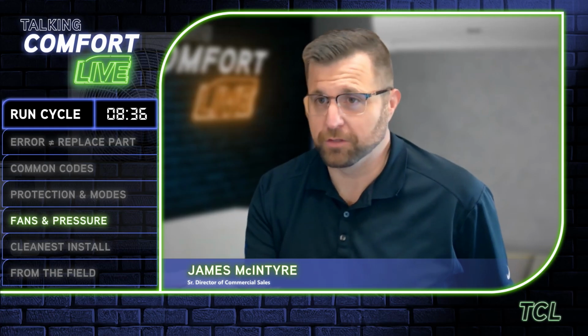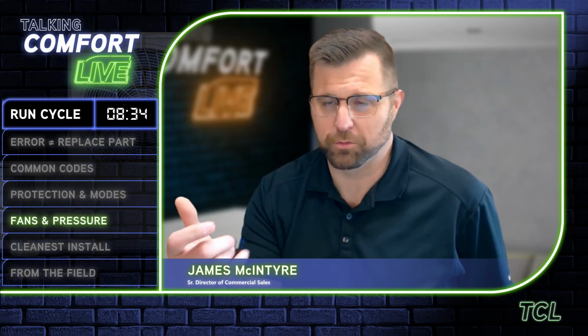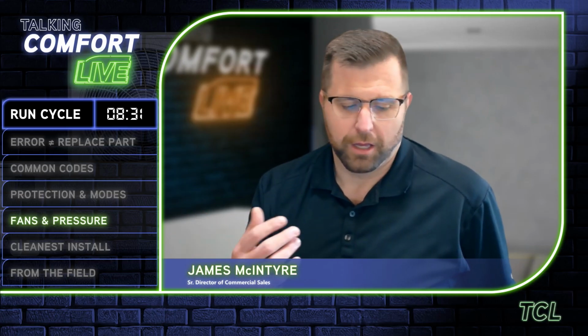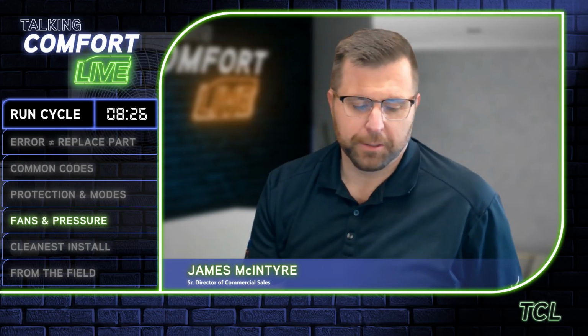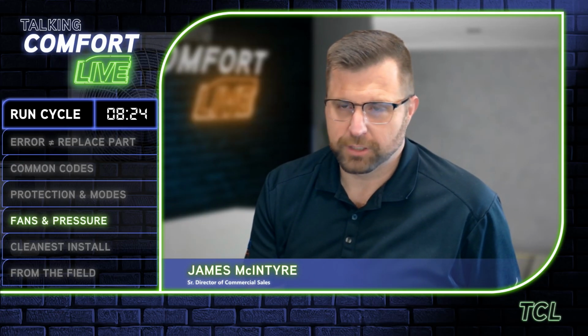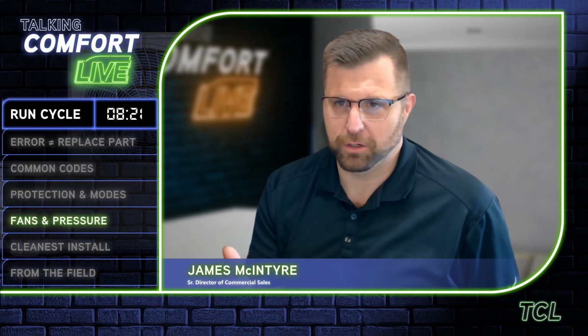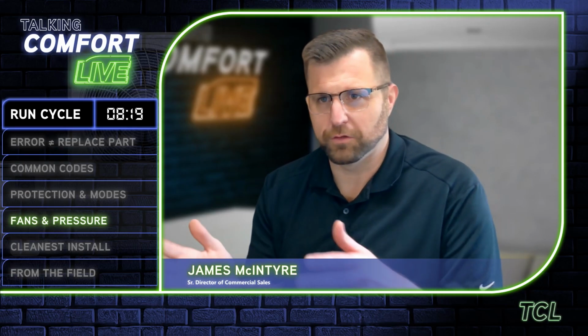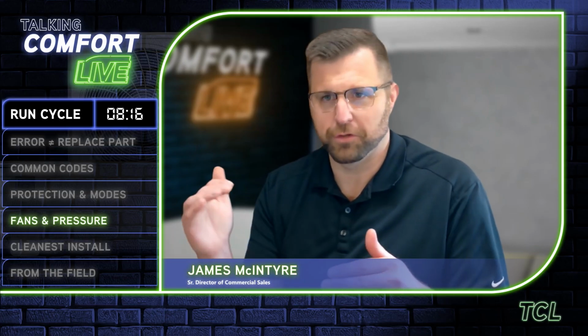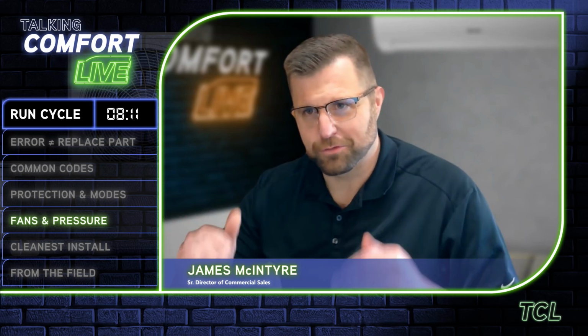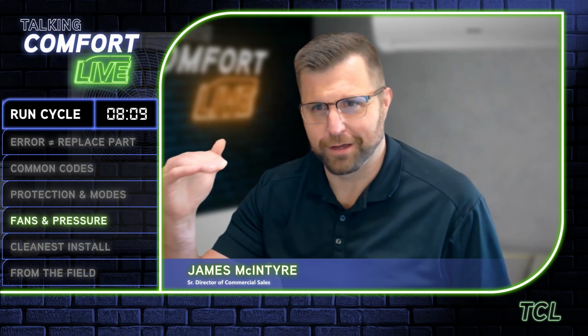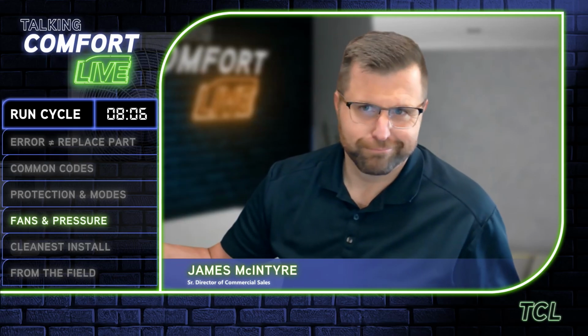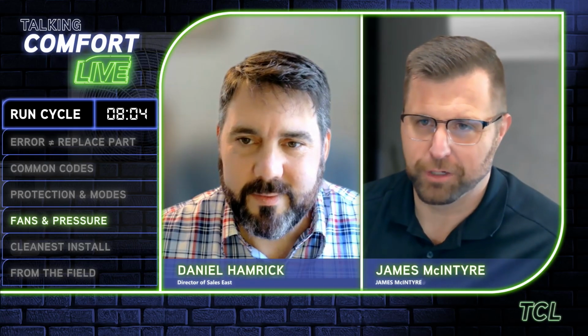One of the tricks there that we regularly communicate is, okay, fine, you got a service tool, that's awesome. You can also use the clamp-on temperature probe for the discharge, and your amp meter to determine your compressor speed. If you turn it off, let it sit for a minute, turn it back on, get a call for cooling, and you see compressor speed continuing to go up and your discharge going higher and higher, and then it hangs out, and then maybe slows down some, and your discharge still remains kind of hot the whole time, it doesn't have enough refrigerant. It can't distribute enough of it.